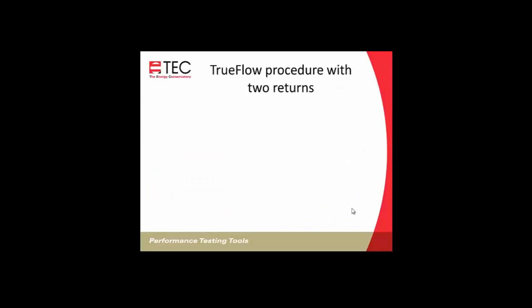So we'll multiply our airflow reading times 1.04 to get our adjusted flow. And the same with this, the inch of water chart. We'll do the same thing with normal system operating pressure and follow that down to our TrueFlow, and at the intersection is our multiplier.